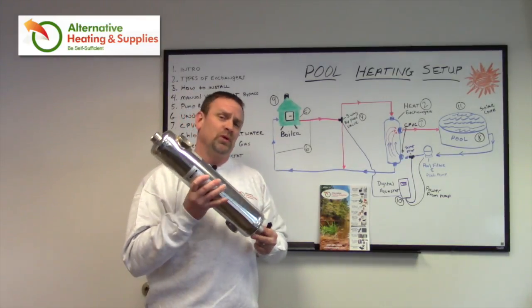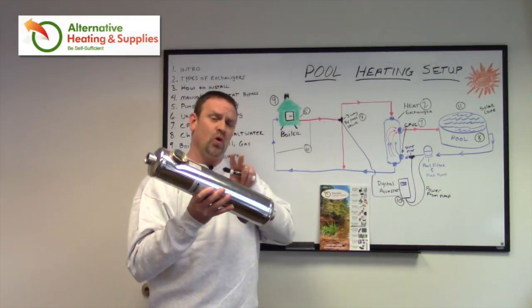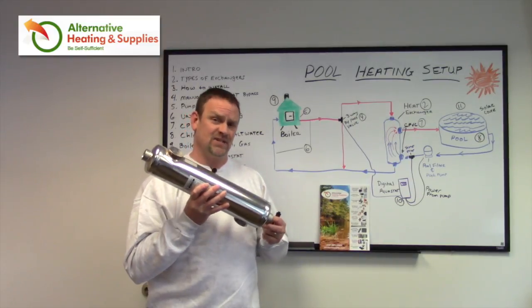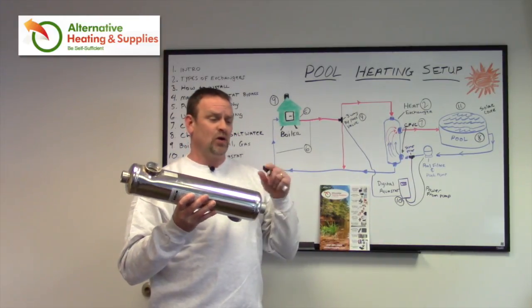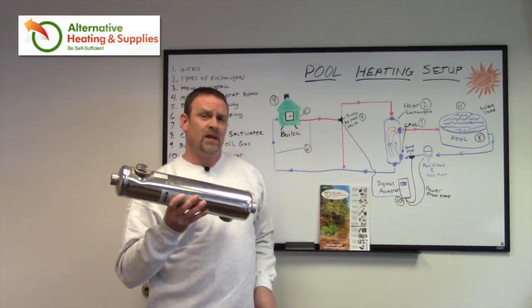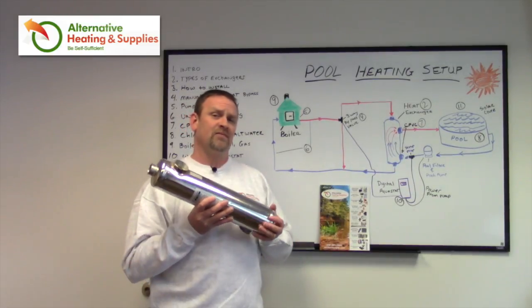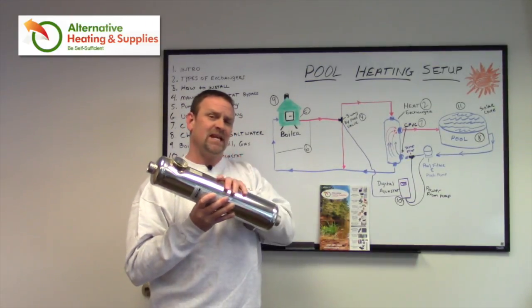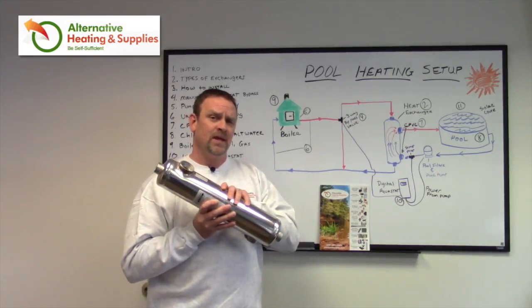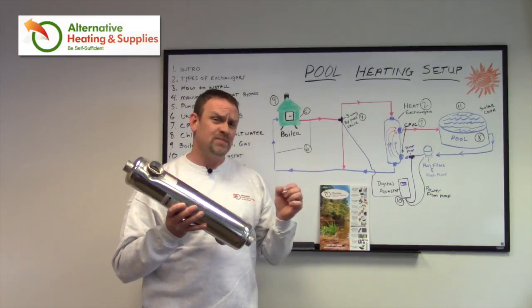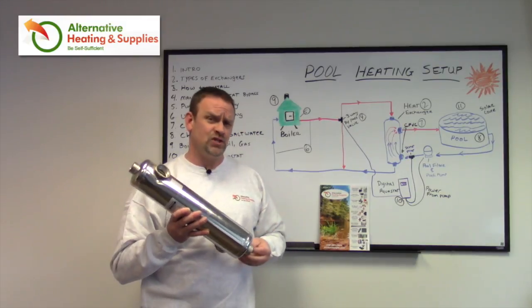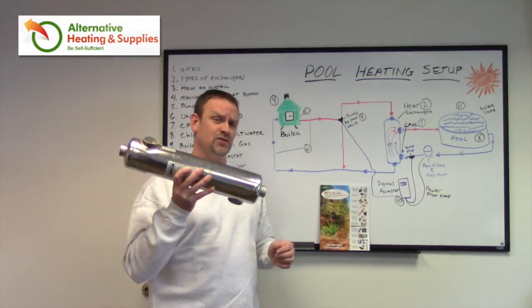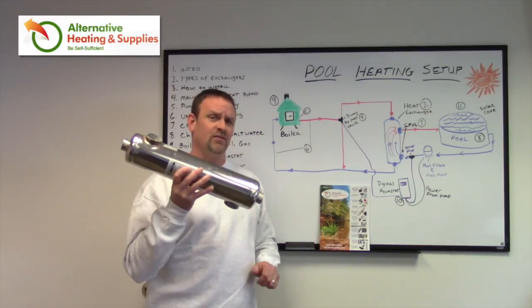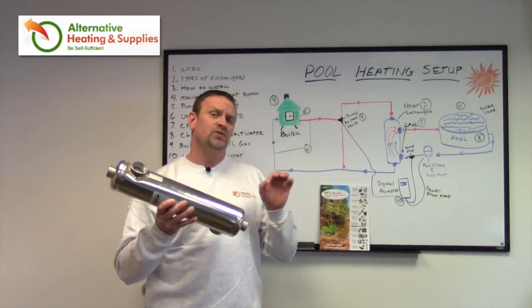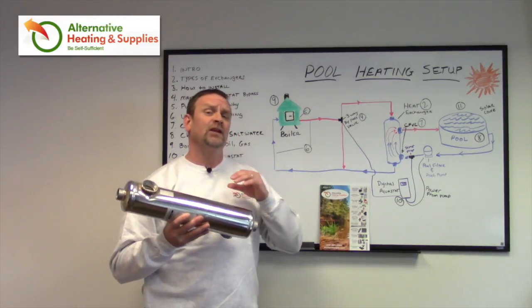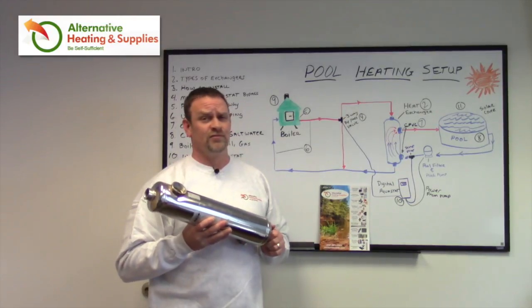What makes a good pool heat exchanger in a tube and shell is the quality of the stainless steel as well as the thickness of it. In this case, my equivalent heat exchangers that I sell compared to this one are about 40% heavier. So my stainless steel is considerably thicker. That works against me sometimes because I lose some of my heat exchange. However, I would rather have the durability and the longevity of a quality heat exchanger over losing a little bit of heat in the pool or taking it a little bit longer to heat up. That's all the real difference is.